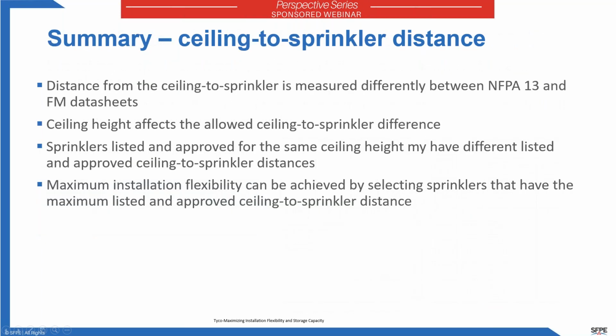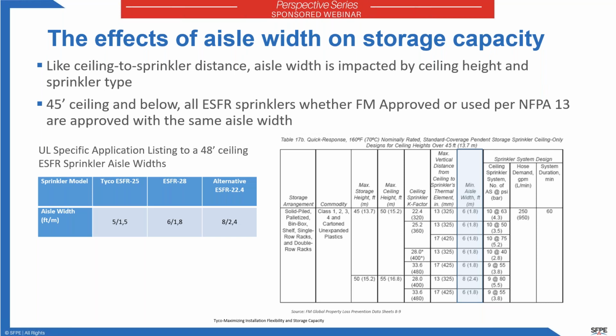So, all right, let's talk about another interesting attribute when it comes to ESFR sprinklers, and that is the attribute of aisle width. So I mentioned that aisle width is the distance between the racks, and like sprinkler to ceiling distance, it's impacted by the ceiling height and the type of sprinkler. So going up to 45-foot ceiling protection, essentially all ESFR sprinklers, whether FM approved or per NFPA 13, have the same aisle width allowances. So essentially, I believe 3.5-foot aisle is the minimum that's allowed up to those ceilings.